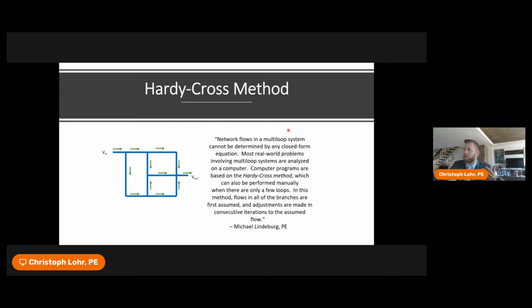And this quote here: network flows in multi-loop systems cannot be determined by any closed form equation. Again, using one equation to solve another. Most real-world problems, such as a hot water return system involving multi-loop systems, are analyzed on a computer. Computer programs are based on the Hardy-Cross method, which can be performed manually when there are only a few loops. In this method, flows in all of the branches are first assumed, and adjustments are made in consecutive iterations to the assumed flow. So again, I'm not making this up.